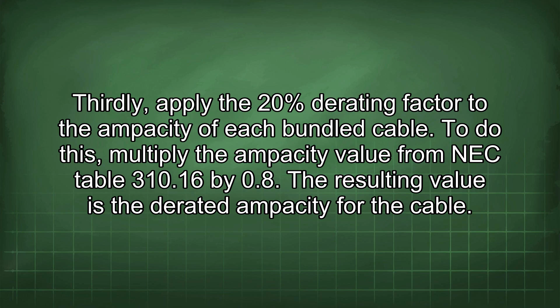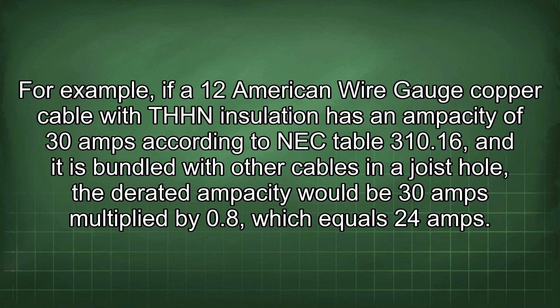For example, if a 12 American wire gauge copper cable with THHN insulation has an ampacity of 30 amps according to NEC Table 310.16 and it is bundled with other cables in a joist hole, the derated ampacity would be 30 amps multiplied by 0.8, which equals 24 amps. It is crucial to ensure that the overcurrent protection device, such as a circuit breaker or fuse, is properly sized to protect the derated cable.